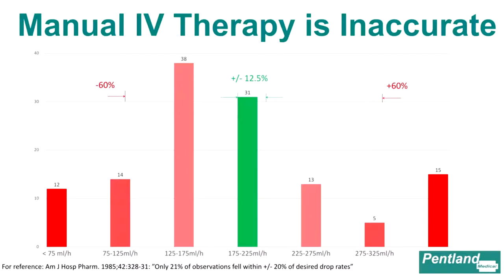You can see in the green bar graph that only 31 out of 129 nurses could reach 12.5% accuracy. Now, the Monidrop device has a better accuracy at plus minus 11%. But look at those extremes. I mean, 20 to 25% of nurses under-infused or over-infused the patients.